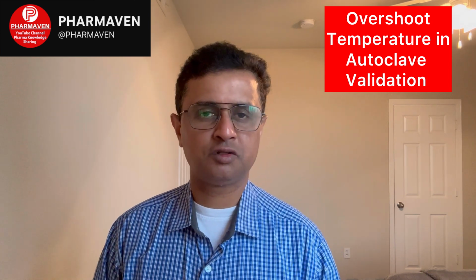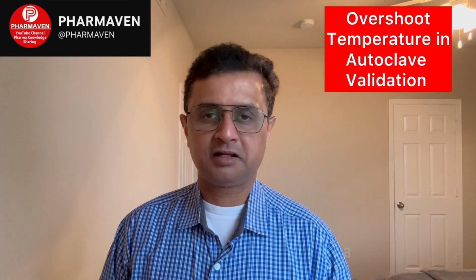Also check what sensor you have used. If you are not using the original sensor of the validator, and you are using local, cheap sensors, then it can have an impact on the overall temperature profile. Also check the calibration of the sensor. We can recalibrate the sensor to understand whether there was any problem with its calibration. For example, if you are calibrating sensors and taking maybe 2-3 cycles, there might be a problem with some of the sensors, which can give erratic or false results. So check the sensor and thermocouple calibration. Check that you have used the same validator that was used in the previous qualification. Practically this should not have any impact, and changing the validator should not matter, but for our reference we must check whether we used the same calibrator or validator to validate the autoclave cycle.